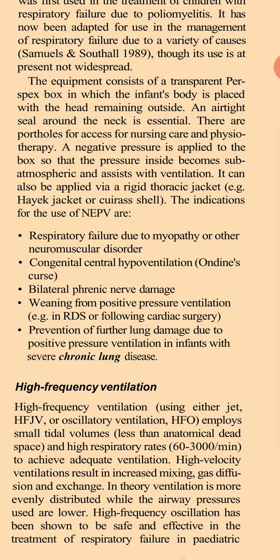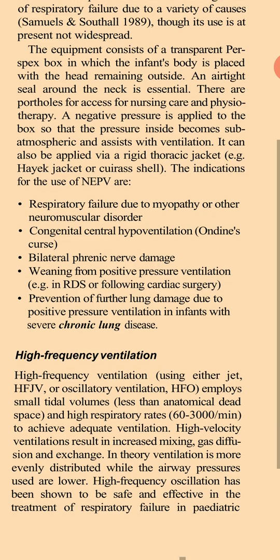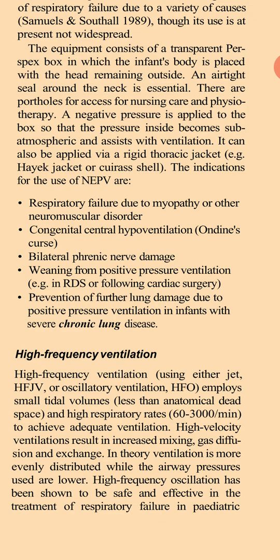The equipment consists of a transparent perspex box in which the infant's body is placed with the head remaining outside. An airtight seal around the neck is essential. There are portholes for access for nursing care and physiotherapy. A negative pressure is applied to the box so that the pressure inside becomes subatmospheric and assists with ventilation. It can also be applied via a rigid thoracic jacket, for example a Hayek jacket or cuirass shell.